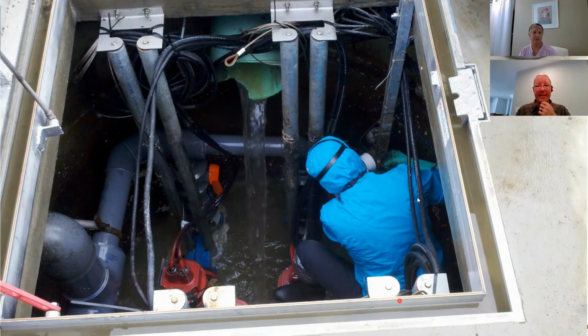They were getting mop heads and other debris coming in from city sanitary. So this poor lady's all masked up in there cleaning out the floats and cleaning out the basin. Not a real great environment. By the way, if anybody knows, most pumps are blue, meaning non-explosion proof. If you get an explosion proof motor, it should be painted red. That's your indication that these are explosion proof motors.